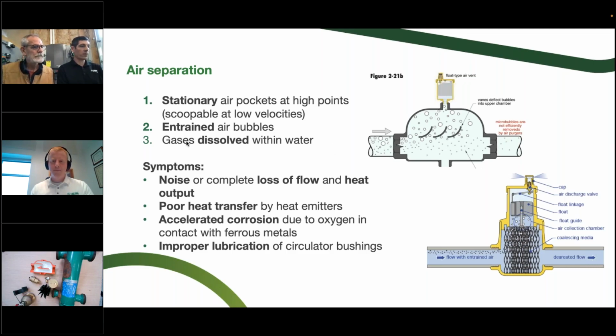And then the last one is gases dissolved within the water. That's an even trickier one that relates to the temperature and the pressure in the system. You could have an air separator that's doing a great job for the first two, but it's in the wrong location and you wouldn't catch that third category. So those are a couple different things. Do you want to demo how the scoop works a little bit there? And then we'll move on to some piping related to that.